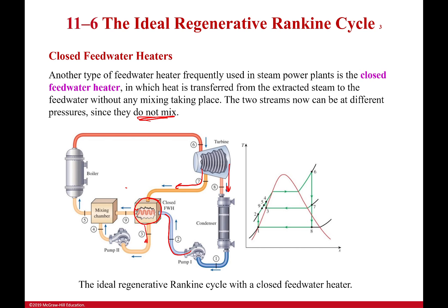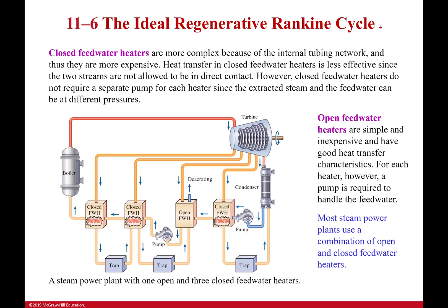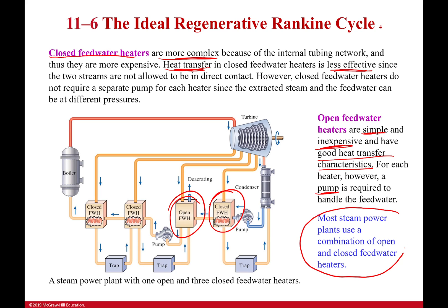You don't have to use one or the other — you can use both: an open feed water heater here and a closed feed water heater there. Closed feed water heaters are more complex because of all the tubes being connected, and heat transfer is typically less effective since there's no direct contact. Open feed water heaters are simple, inexpensive, and have good heat transfer characteristics; however, each one requires a pump to get the water to the right pressure. So you can use some combination of the two, and most steam power plants do use a combination.